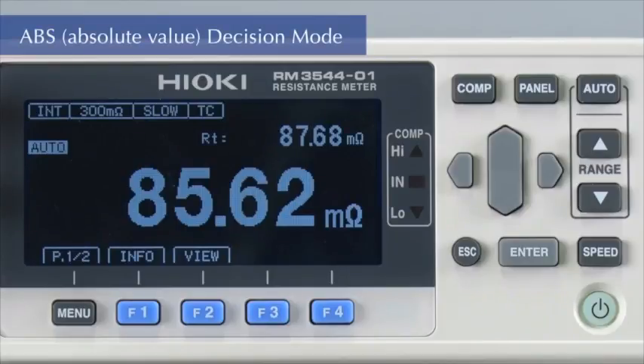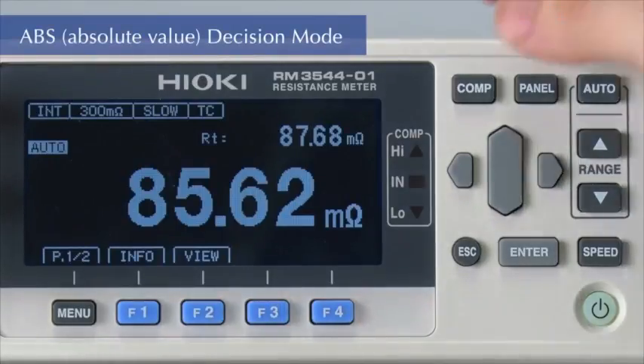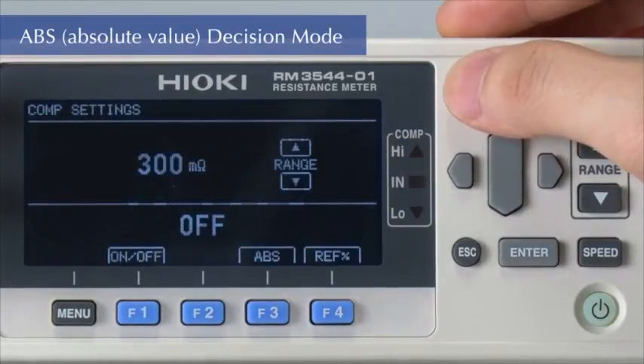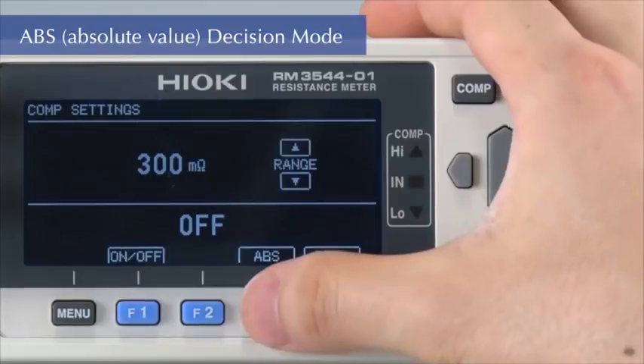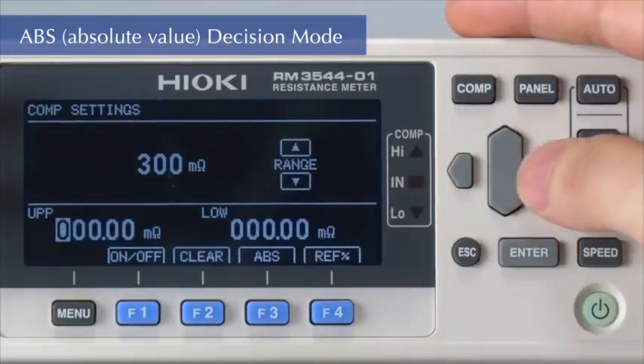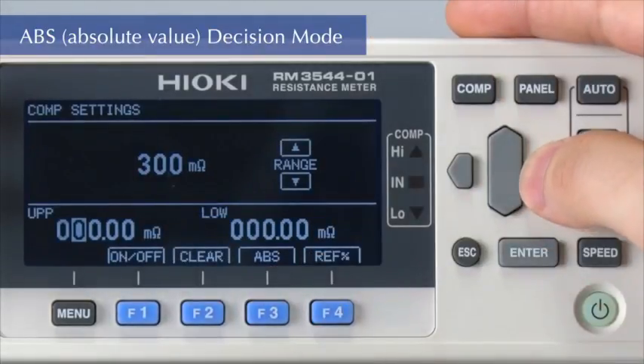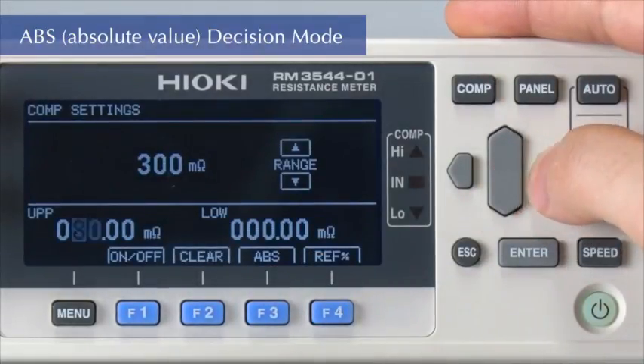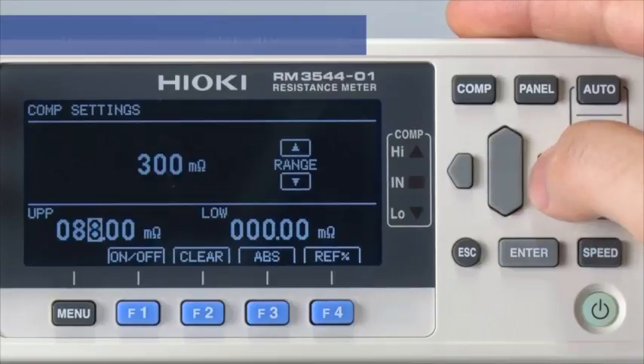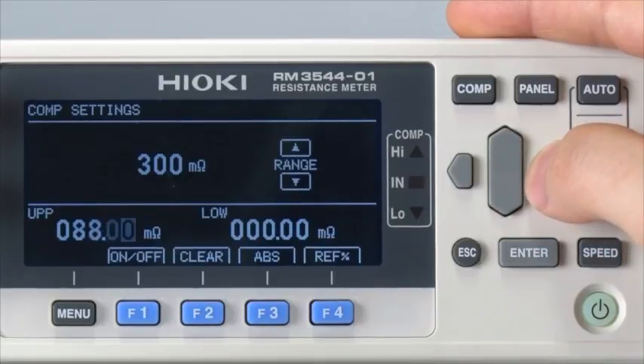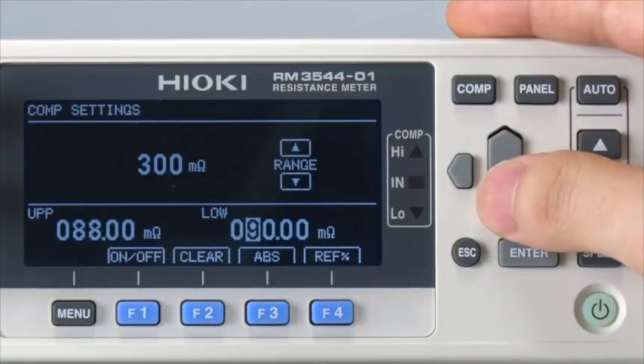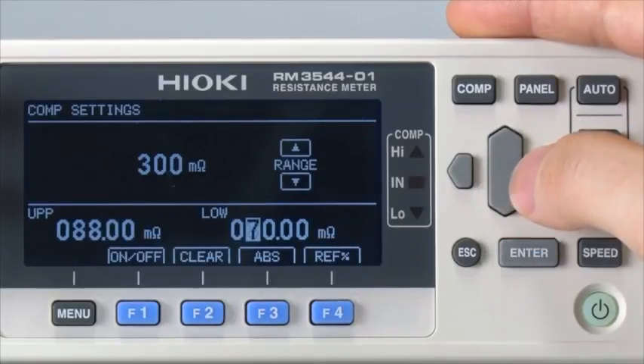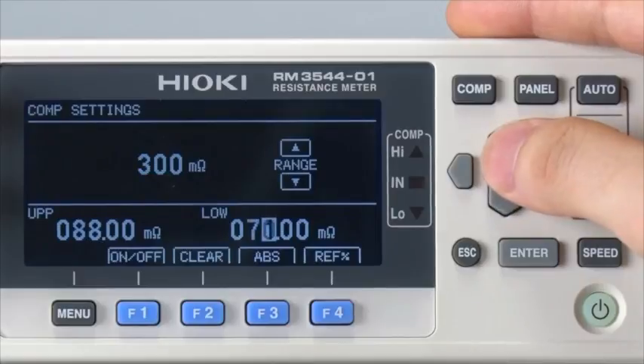To make a comparative judgment using the upper and lower thresholds, make settings in ABS mode. Here we will set the upper threshold at 88 milliohms and the lower threshold at 71 milliohms.